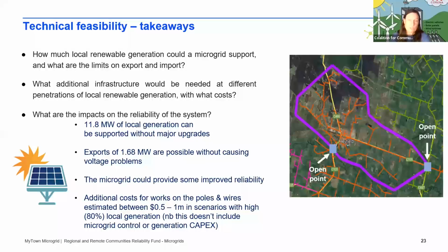We did some technical modelling - the university looked at electrical currents and the maximum current the system here could take before reaching its thermal loading. Without impacting reliability, almost 12 megawatts of local generation can be poured in. You can export up to 1.6 megawatts before you start to get voltage problems - that becomes relevant when you see the size of solar needed to fully run this as a microgrid.